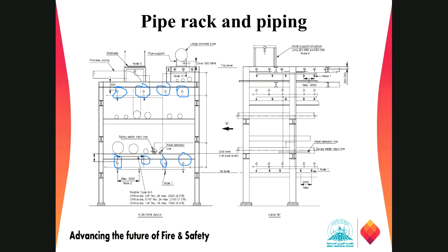It is protecting the equipment also, and sometimes it is for mitigation. As I said, this is a closely packed area. In a closely packed area, we always assume there are some flammable vapors present in some quantity, below the fire range. But if those gases and vapors come into the flammable range, there are gas detectors installed in those areas. Those gas detectors will send a signal to the process unit area that there is an accumulation of gas. So what will happen at that time?